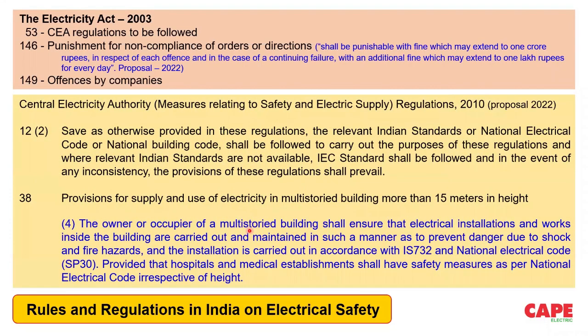Now, coming to the central CEA measures relating to safety and electric supply, of course, I am referring to the proposal 2022. I don't know whether it will be finalized or not, but the same proposals have been there since 2016 or 2018. Save as otherwise provided in these regulations, the relevant Indian standards and the National Electrical Code or National Building Code shall be followed. Basically, whatever is not contained in the regulation, you can refer to the code of practice of the Bureau of Indian Standards to achieve safety. That means the regulation is mostly discussing generation, transmission, distribution, and mostly up to the point of commencement of supply. Of course, there are regulations which are applicable inside the house as well. So whatever subject is not covered in the regulation, you can refer to the code of practice.